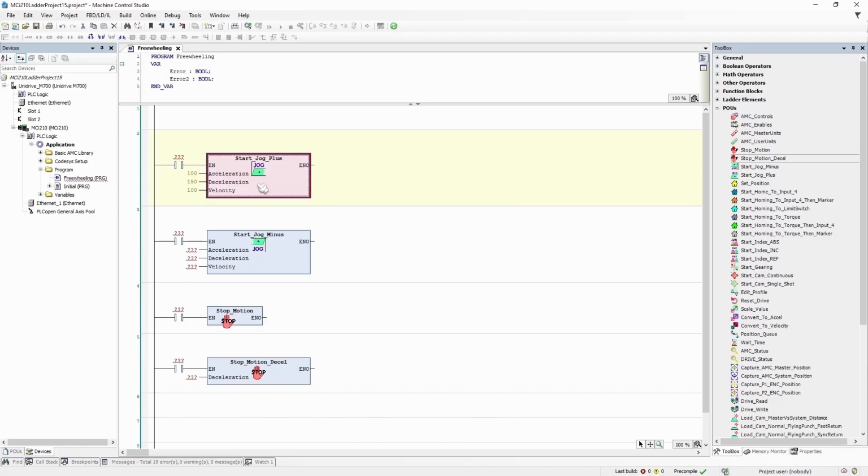However, there is an exception to this. If you look at the AMC user unit block that I talked about in a past video, you'll notice that if you're using hardware version 2 block, you can actually change this acceleration and deceleration units to be time. So it could be that this could be 100 milliseconds and this is 150 milliseconds. So if you have it set to time, well, then it's exactly the opposite. It's actually slower to use a big value. But the default way the drive behaves is bigger value, faster you accelerate. Okay? So I'm just going to put the same value in all of these.